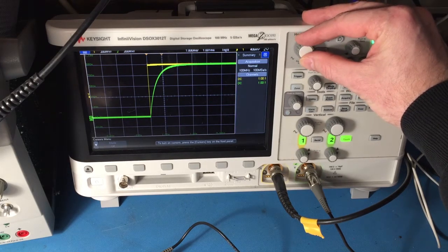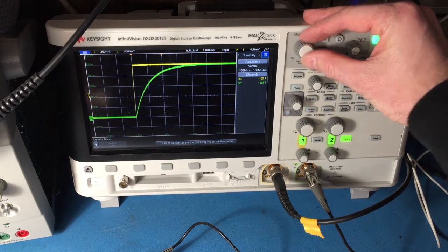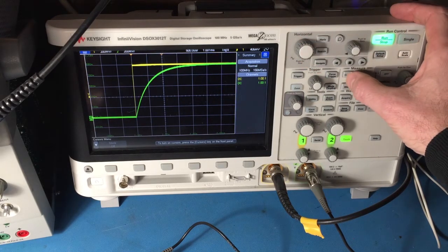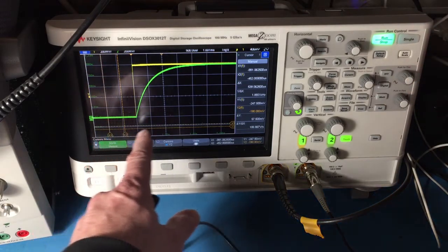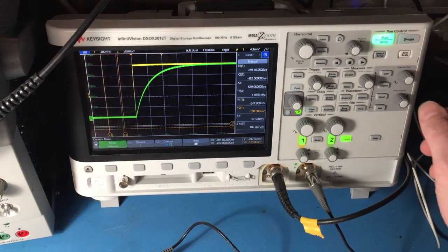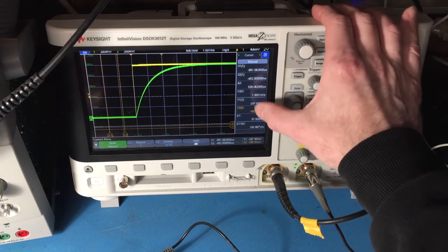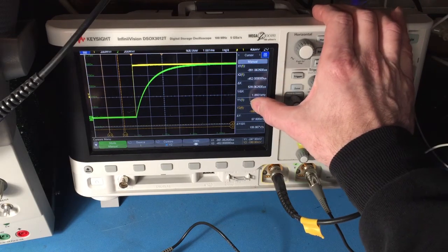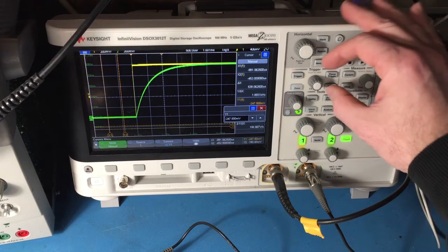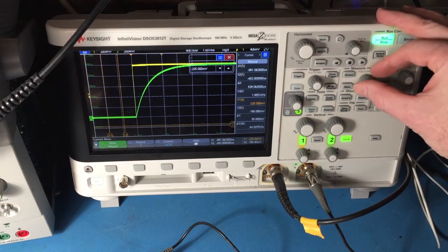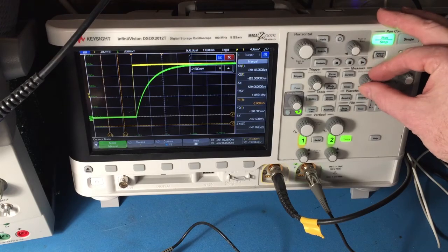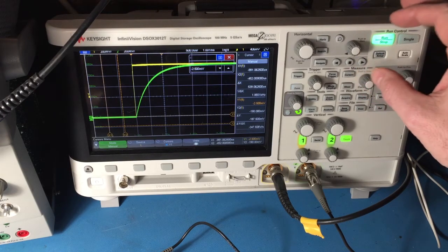So I'm going to make my time base a little bit smaller so I can see some more of the waveform. On this oscilloscope, if I push the cursor button, it brings up these cursors, which are little lines that I can move back and forth. When I do that, they mark off time and voltage. The first one I want to do is set my voltage cursor. I'm going to set the baseline cursor down here. And if we look at the values here, it might be a little small, but it's confirming that we're at 0 volts, plus or minus a few millivolts.